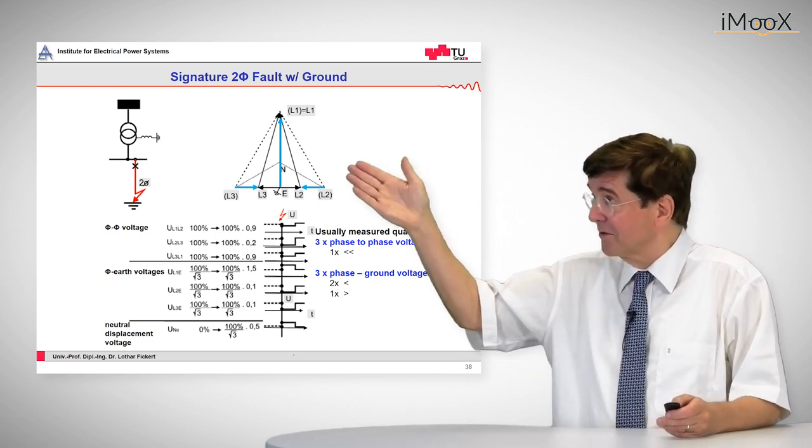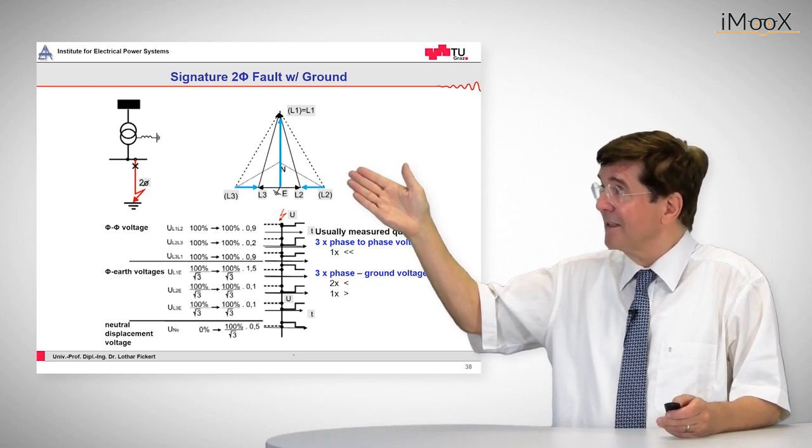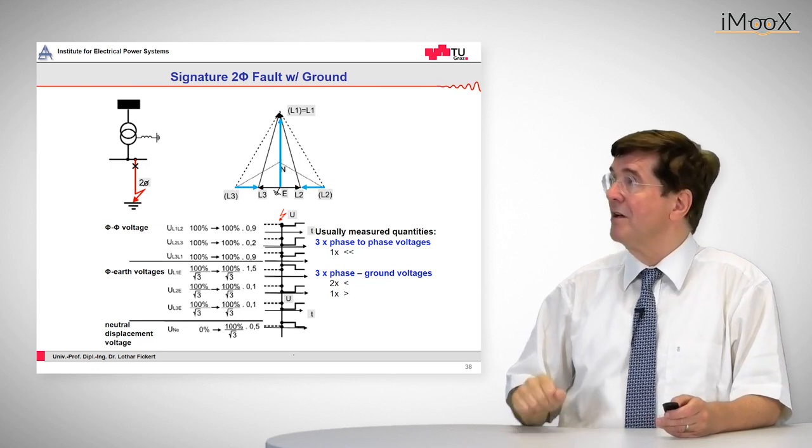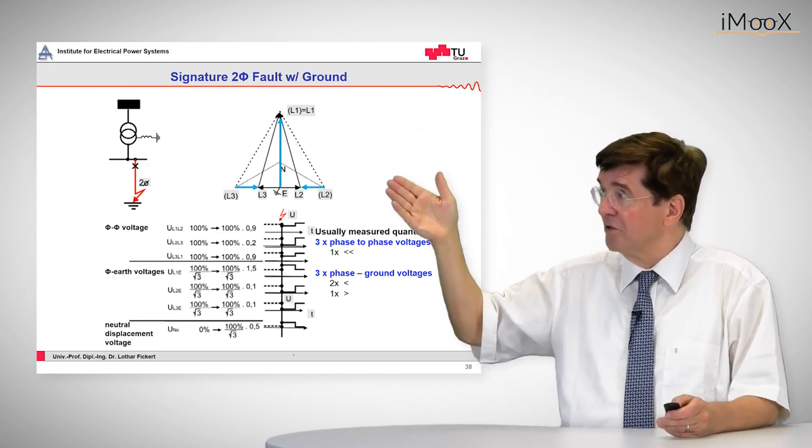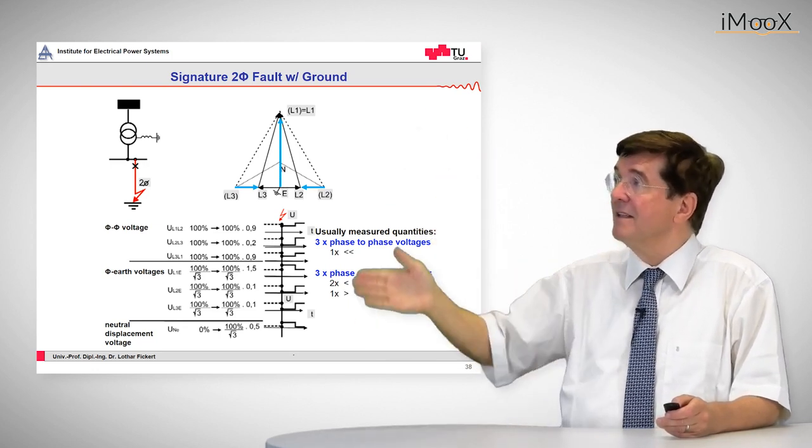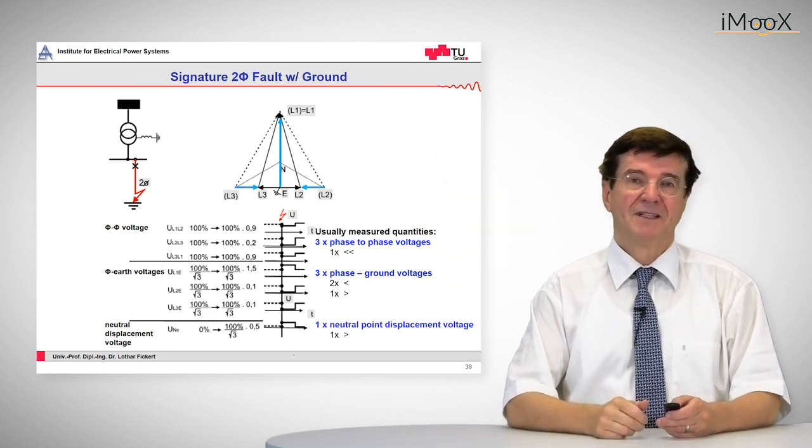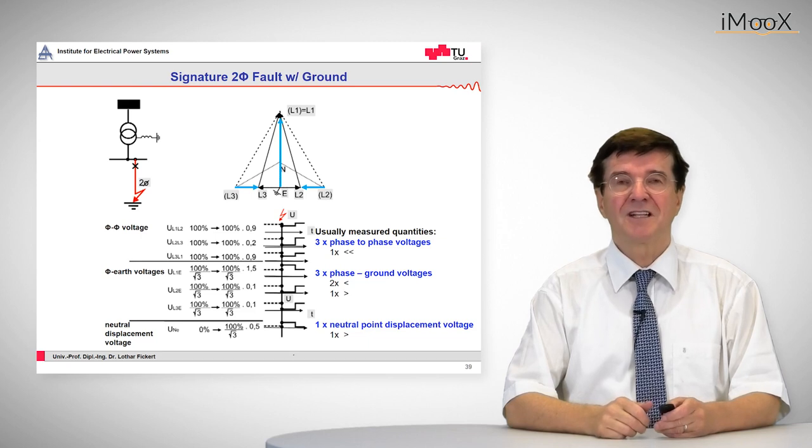The reason is when we look into the voltage triangle that before the fault the line to ground voltage in L1 was L1 to neutral and now this has risen up by 50%.